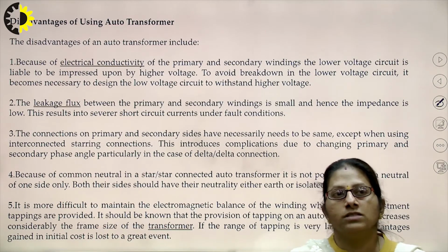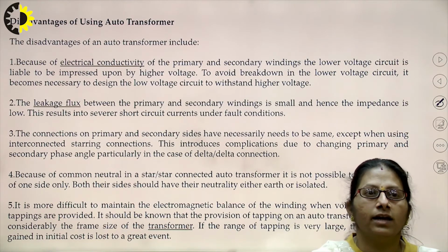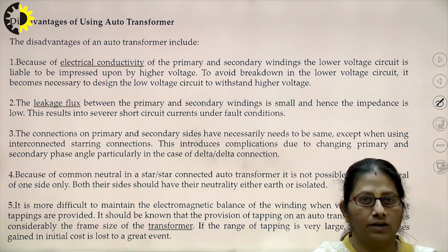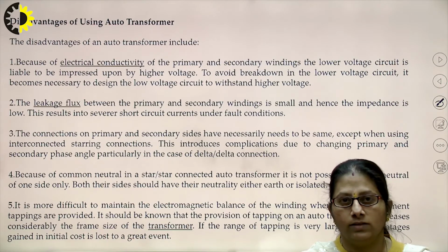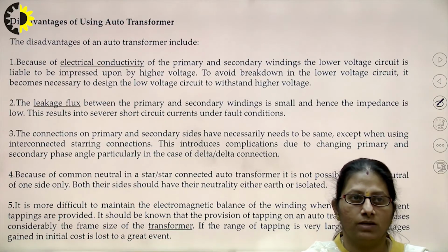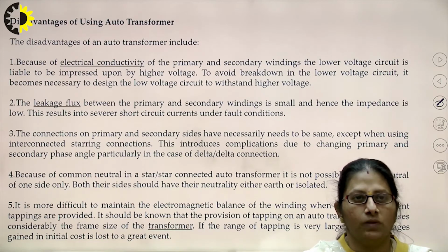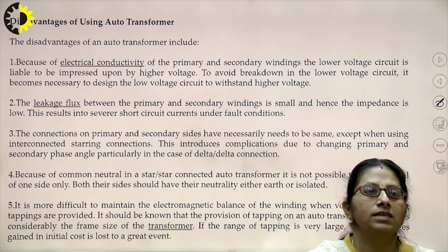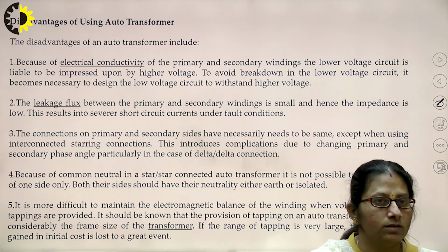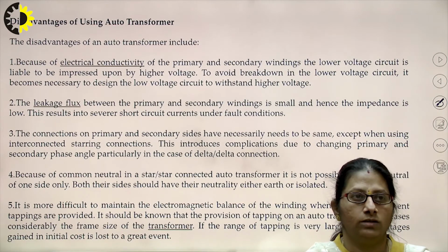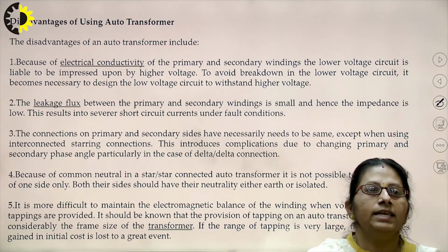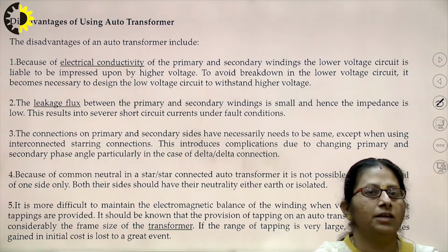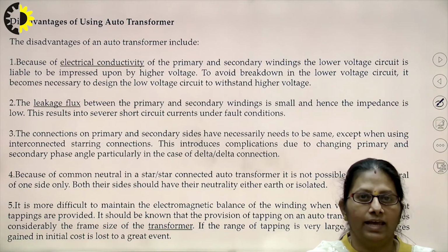The very first disadvantage is that, because of the electrical conductivity between the primary and secondary winding, the lower voltage circuit is liable to be impressed upon by higher voltage. To avoid breakdown in the lower voltage circuit, it becomes necessary to design the low voltage circuit to withstand higher voltage.